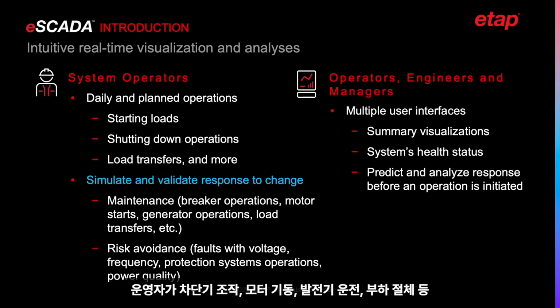When an operator needs to perform changes in the operation and maintenance, such as a breaker operation, motor starts, generator operations, load transfers, and more, they can simulate and validate the response of the electrical network and understand risks and avoid unforeseen conditions such as faults with voltage, frequency, protection system operations, and power quality issues.